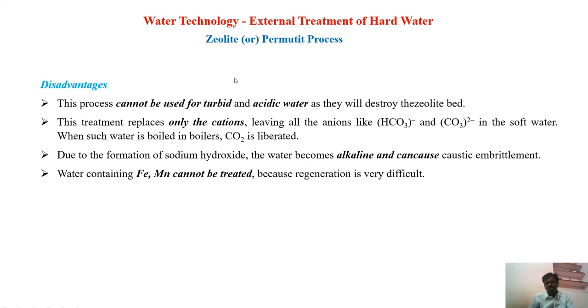In summary: zeolites available naturally are called zeolites; those prepared in the laboratory are called permutit — and permutit has higher efficiency. Hard water is passed through the zeolite bed where sodium ions exchange with calcium and magnesium ions. After all sodium ions are exhausted, the bed is regenerated by washing with 10% NaCl (brine), which restores the sodium ions so the zeolite bed can be reused again and again. The advantages and disadvantages have been discussed above.